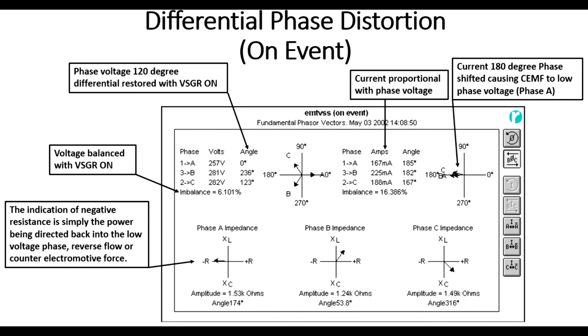With the voltage correction on, we'll see that the phase angles here are 120 degrees within a couple of degrees from each other. The voltage imbalance is now 6%. We'll notice that the impedances down on the bottom here are all very close to each other. And the indication of negative resistance on the left here is simply power being directed back into the low voltage phase, which was phase A. As you look up to phase A here, we'll see the voltages now are 257, 281, and 282. To the right of that, you'll see the three little arrows or electrical vectors called phasors. You'll see that they're virtually equal, and they have the 120 degree phase differential.